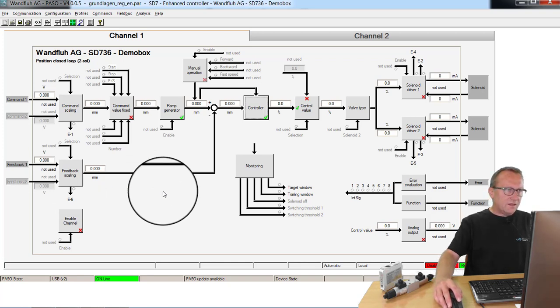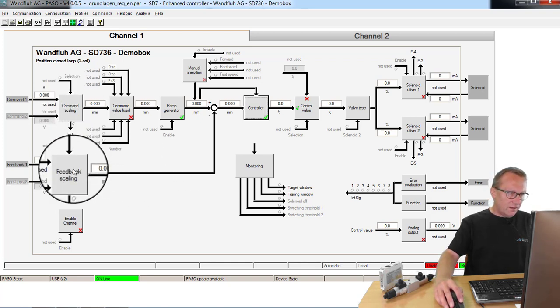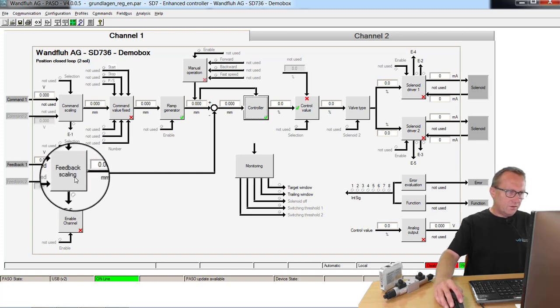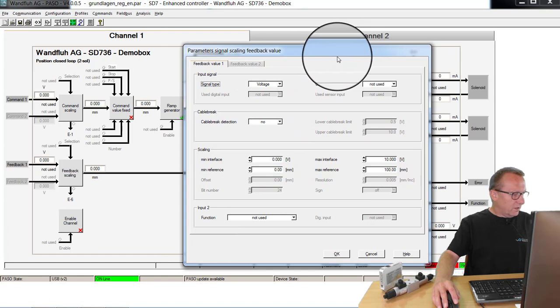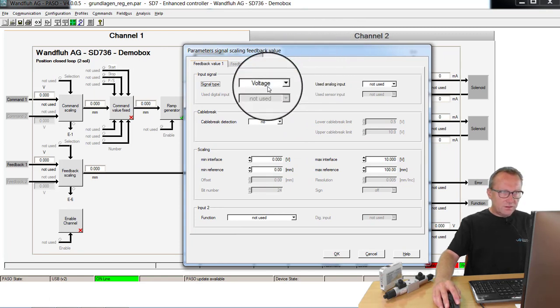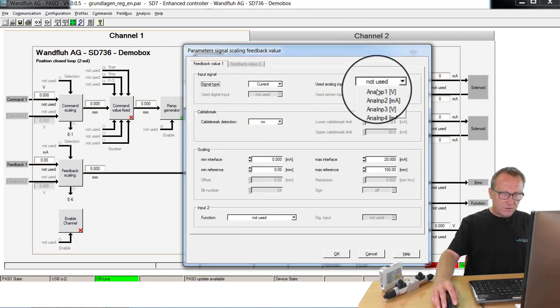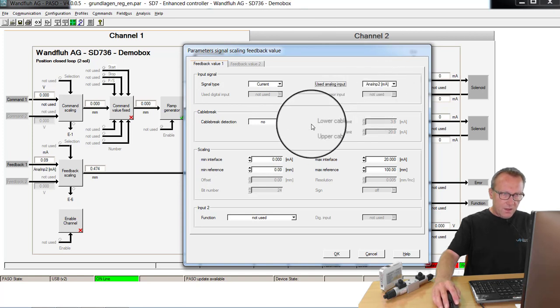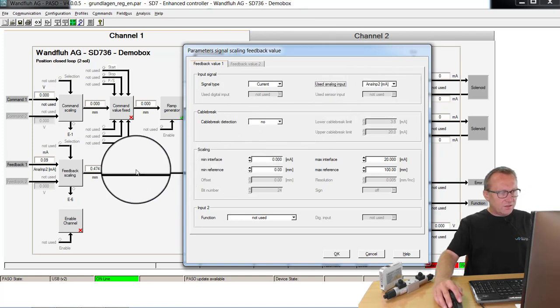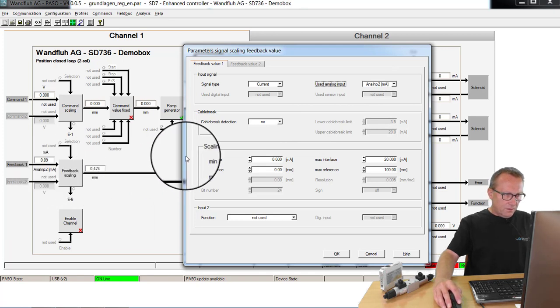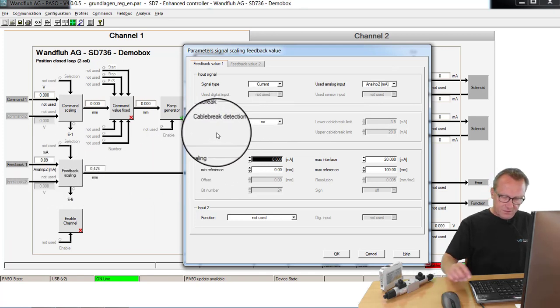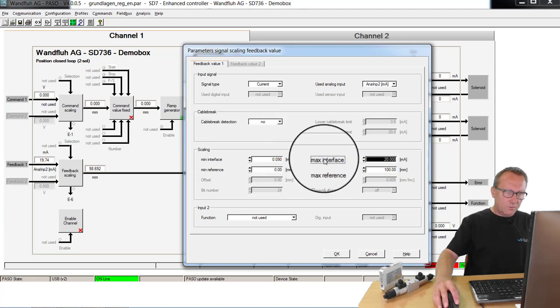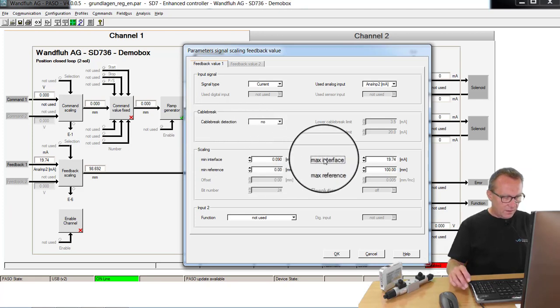Next step is to set the scaling for the command and the feedback value. We start with the feedback value. In our application, the feedback value is a current signal connected to analog input 2. If the cylinder is in the inside position, the signal from the sensor is 19.74 milliamps.